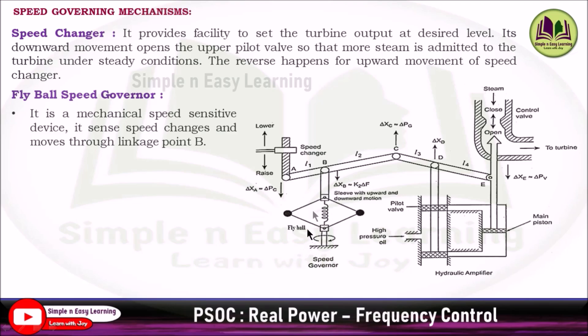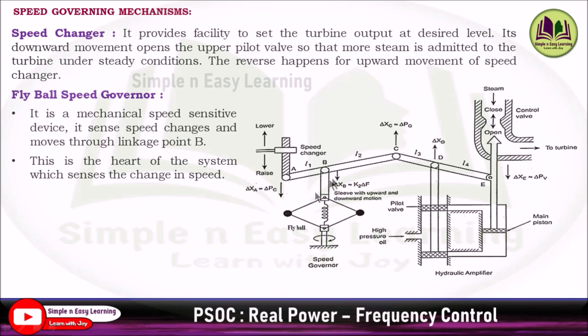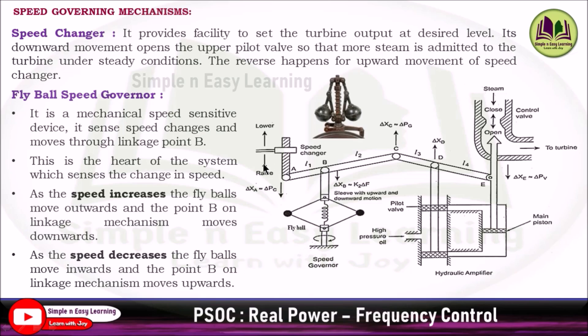The fly ball speed governor is a mechanical speed-sensitive device. It senses speed changes and moves through linkage point B — this is the heart of the system. There are two fly balls. As speed increases, A moves downwards, the fly balls move outwards, and point B of the linkage mechanism moves downwards. As speed decreases, the speed changer moves upward, the fly balls move inwards, and point B moves upwards.